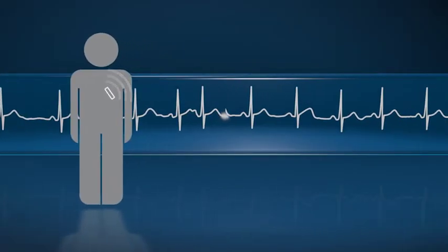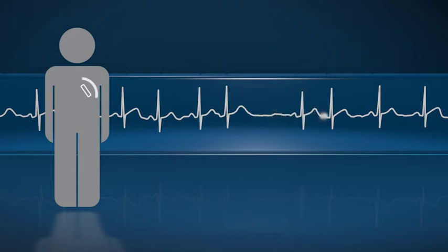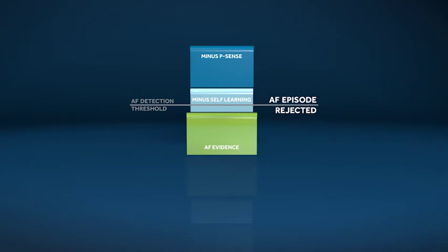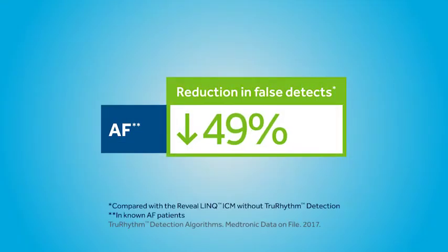In atrial fibrillation, TruRhythm Detection's exclusive self-learning algorithm means you get tailored detection for each patient. TruRhythm learns your patient's unique rhythms and adapts its detection threshold automatically throughout the day, rejecting inappropriate AF episodes. This streamlined data means a significant reduction in reviews by cutting AF false detects up to 49%.